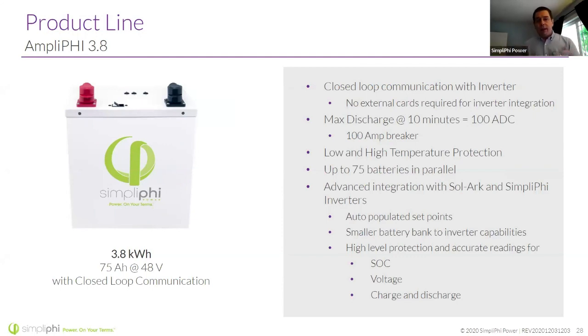Now, this is pretty cool. It enables an increased maximum discharge of up to 100 amps, because if the battery can communicate what's going on, it can release more potential, and the inverter can draw more potential. It's also got the ability to do low and high temperature protection.